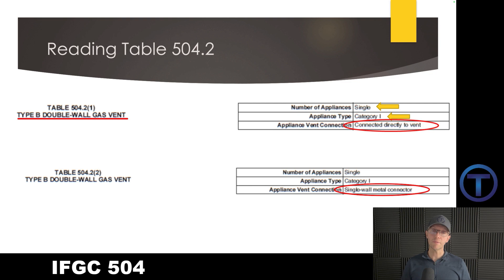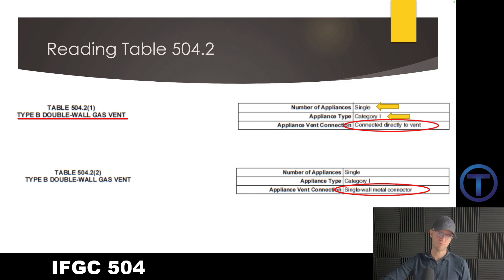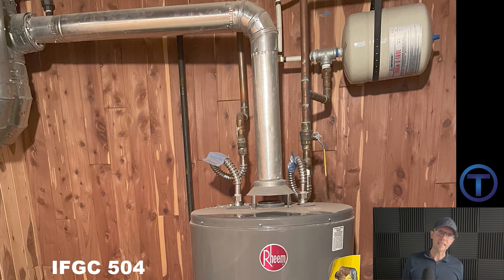These are single appliance tables. So I've got one appliance and it's Category 1. You'll find that on a smaller table across the top of the page — single appliance, Category 1, and then the appliance vent connection. It is connected directly. Or there are other tables that say we have a single wall metal vent connector. So you can either take that B vent right down onto the top of the appliance, where the whole thing is the same type of vent, or sometimes we have the double wall B vent and a single wall connector. That's probably the most common way we handle it.